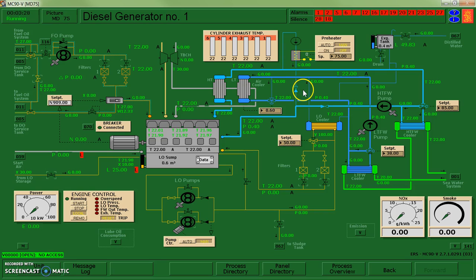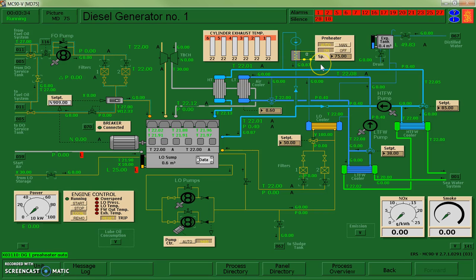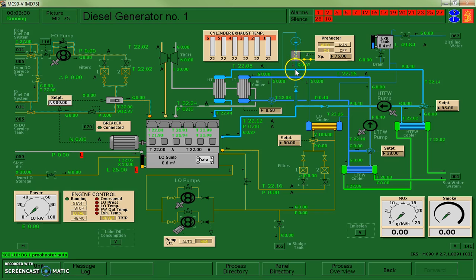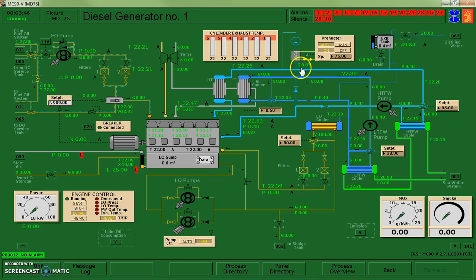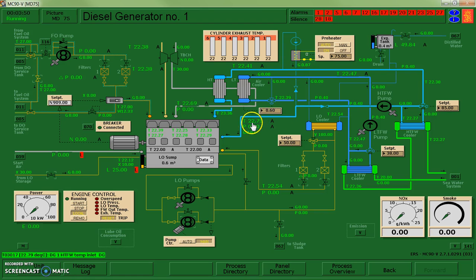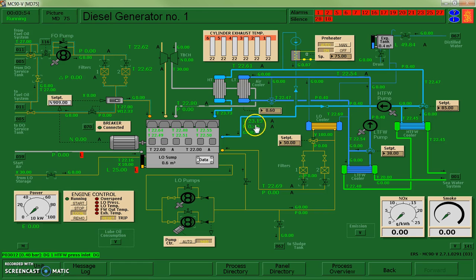The piece that I want to start right away is to turn on my preheater. So I turned on my breaker for that. What I have now is the ability for a little circulating pump to start circulating water through the diesel generator and allowing a little bit of warm up. So you can see it's starting to warm up inside. And that will help protect the engine from a harsh cold start.